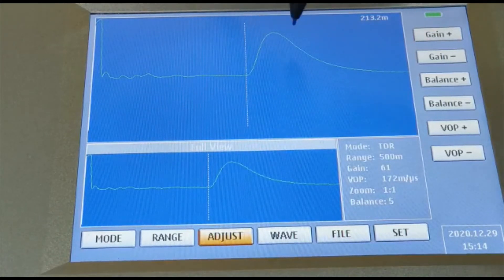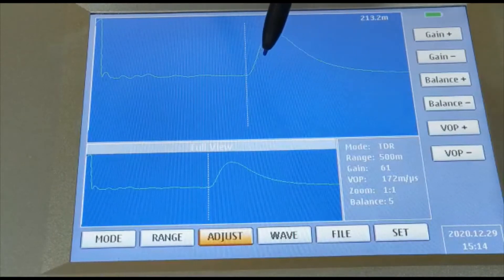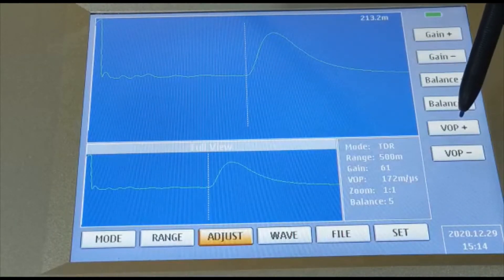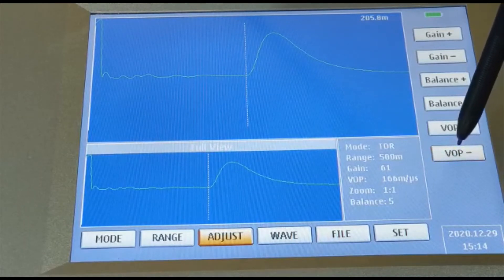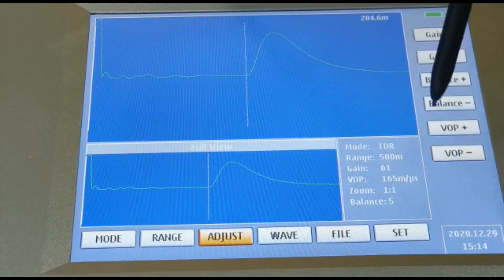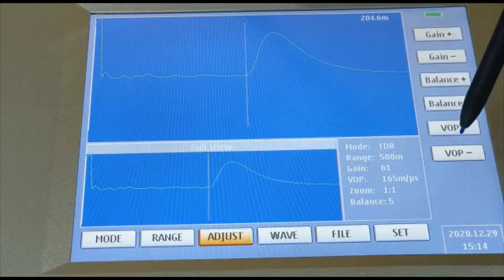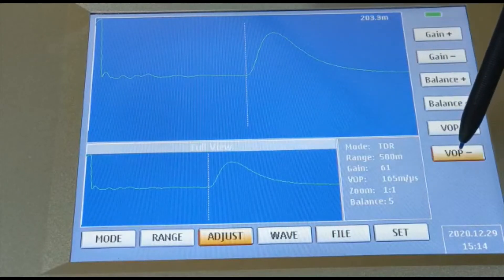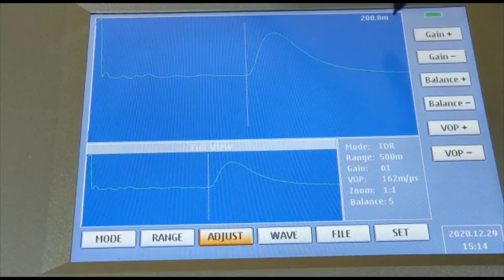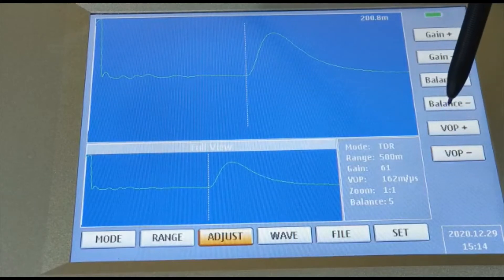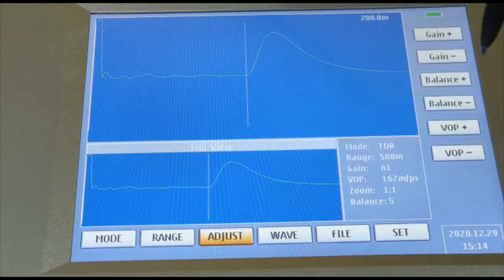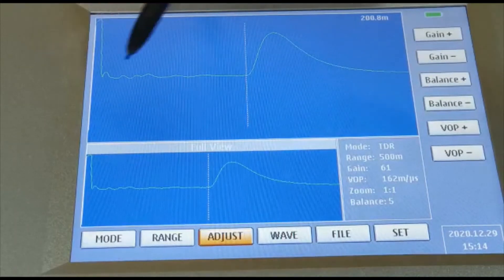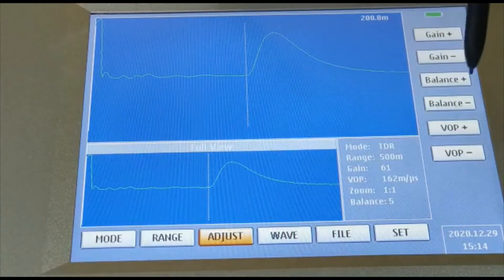We have a 200 meter cable here and the fault is open, showing the open waveform. Based on the insulation of the cable, you can set different VOP (velocity of propagation) values so that you can accurately find the distance to fault. The cable is 200 meters, so based on the cable insulation we set the accuracy to 200 meters by fixing the velocity of propagation. If the curve is off balance, you can adjust it.